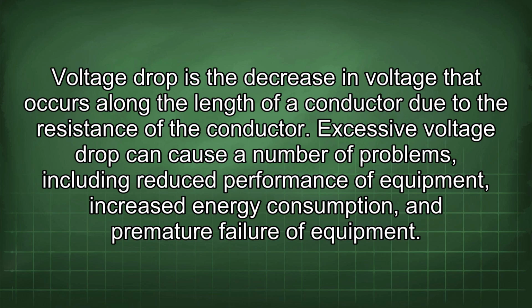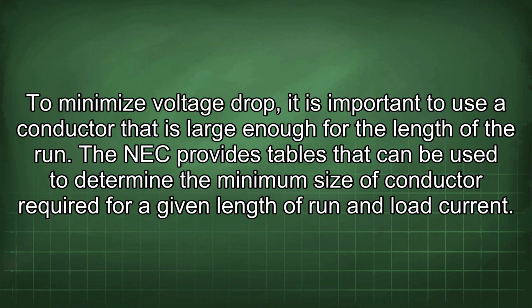Excessive voltage drop can cause a number of problems, including reduced performance of equipment, increased energy consumption, and premature failure of equipment. To minimize voltage drop, it is important to use a conductor that is large enough for the length of the run. The NEC provides tables that can be used to determine the minimum size of conductor required for a given length of run and load current.